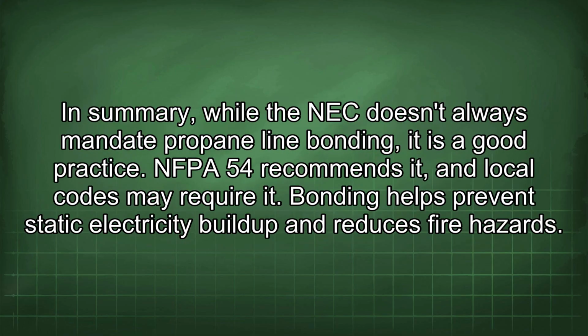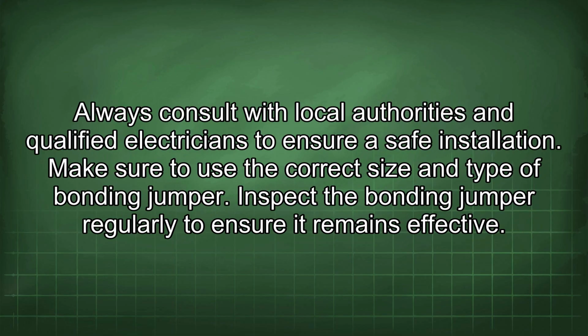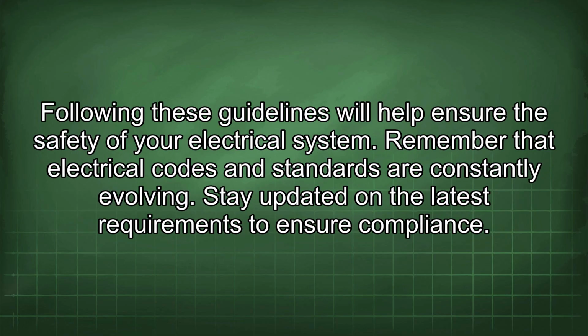In summary, while the NEC doesn't always mandate propane line bonding, it is a good practice. NFPA 54 recommends it, and local codes may require it. Bonding helps prevent static electricity buildup and reduces fire hazards. Always consult with local authorities and qualified electricians to ensure a safe installation. Make sure to use the correct size and type of bonding jumper. Inspect the bonding jumper regularly to ensure it remains effective. Following these guidelines will help ensure the safety of your electrical system. Remember that electrical codes and standards are constantly evolving. Stay updated on the latest requirements to ensure compliance.